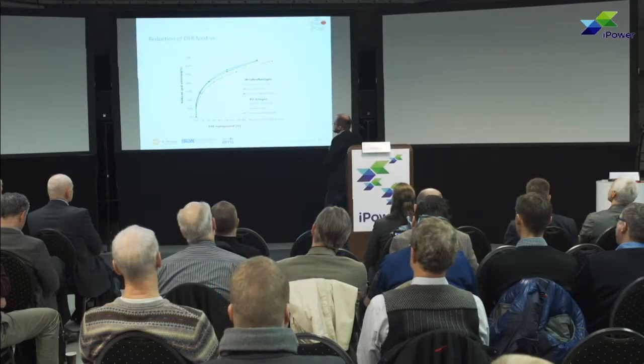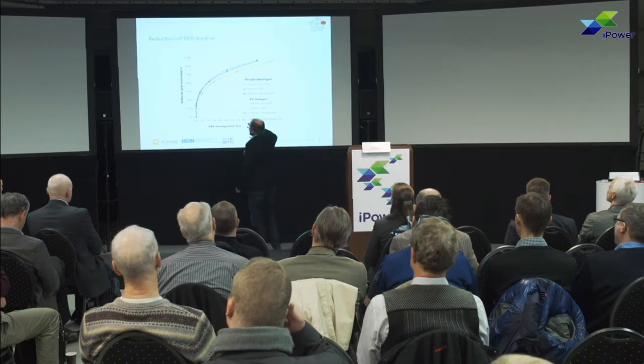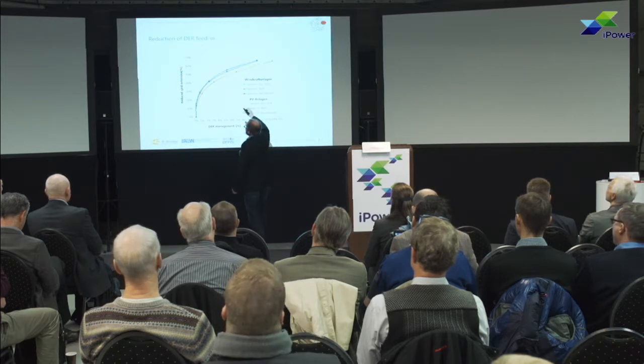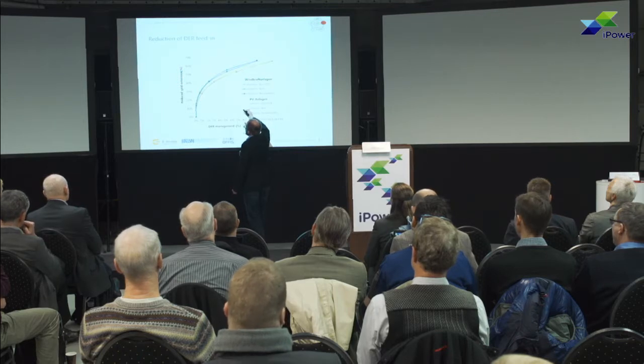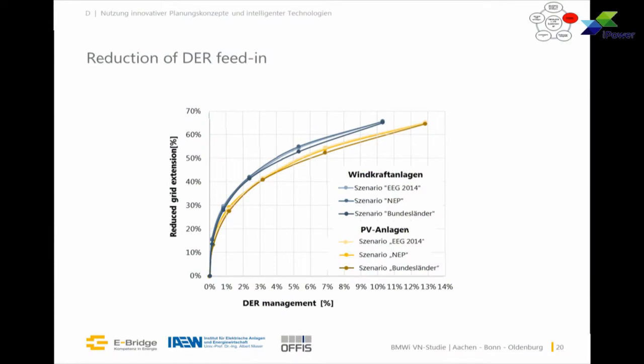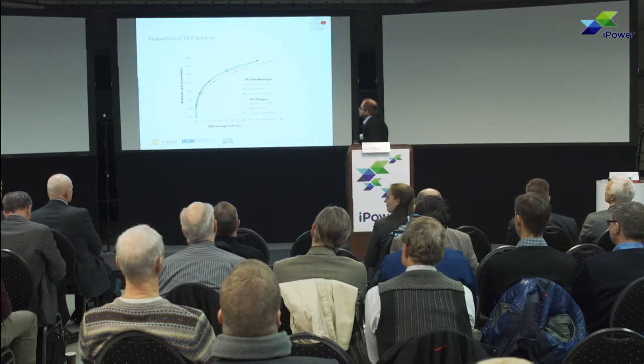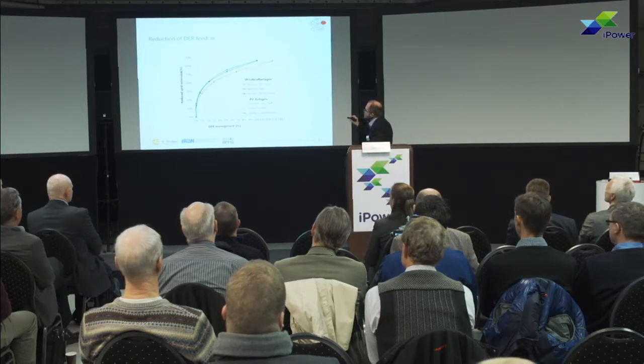The interesting thing is if you cut, and we said okay, 3% for us - if you cut like 3% of the DER peaks, which isn't a lot because how many times do those peaks occur, and you plan your grid for those peaks - if you cut them, you may change your total planning, and that reduces up to 50% of the overall grid extension. Remember those thousands of kilometers across individual voltage levels. So that's just one tiny step which saves a lot of grid extension. Not necessarily money, because you have to deal with energy management and control of the DER to cut their generation. But that's what I'm going to go deeper into in the further slides.